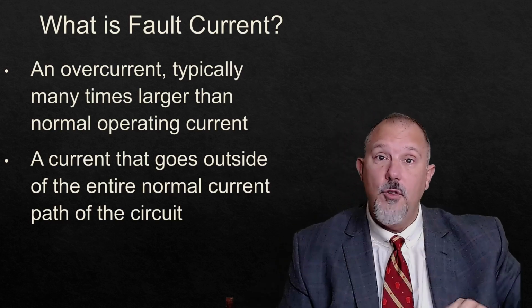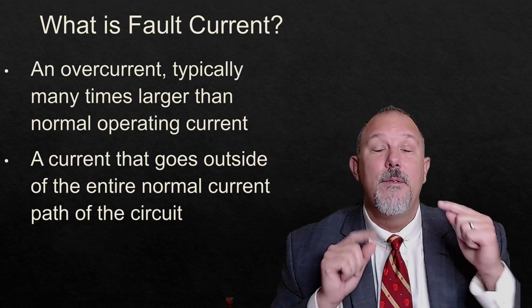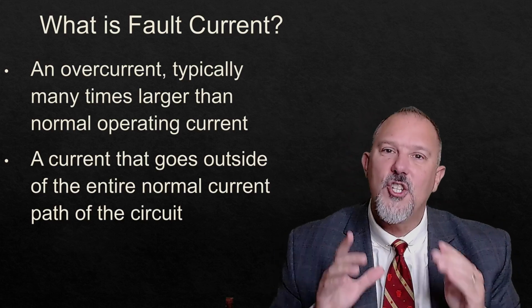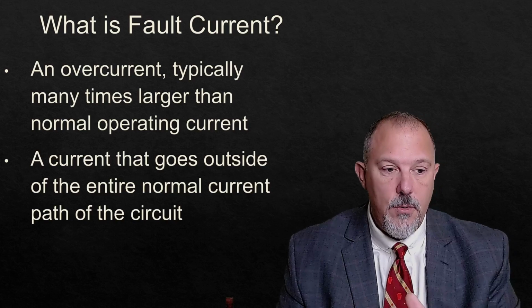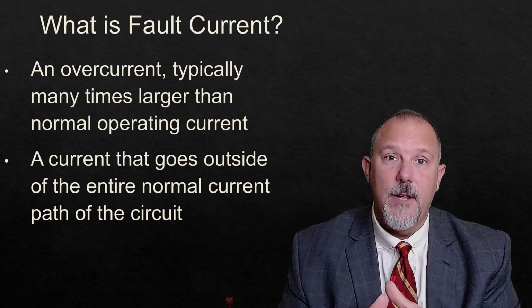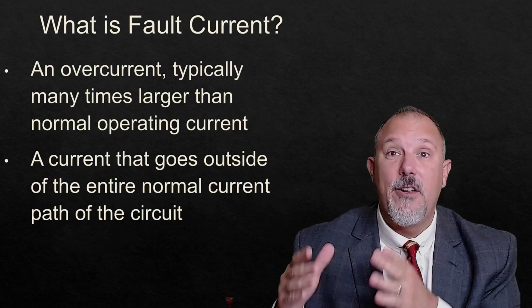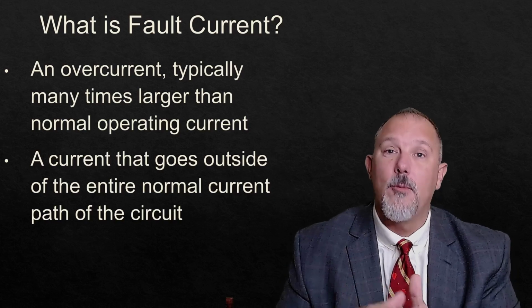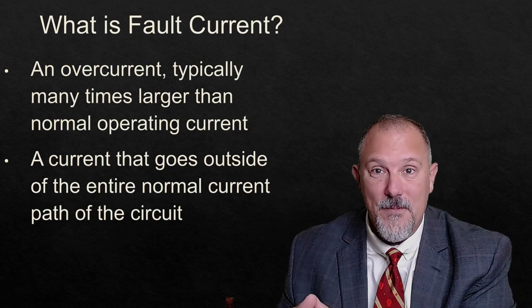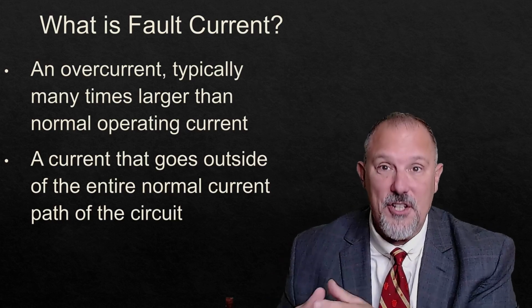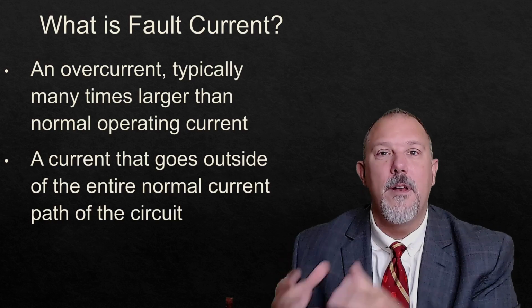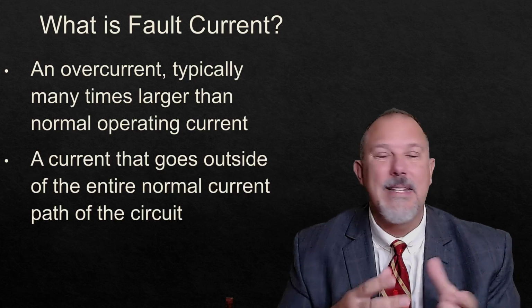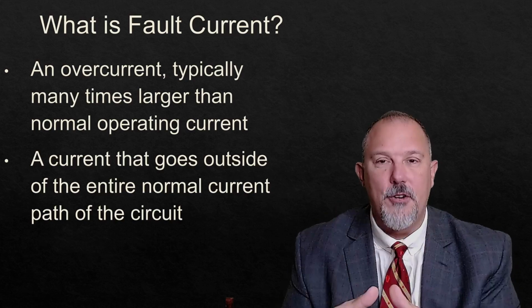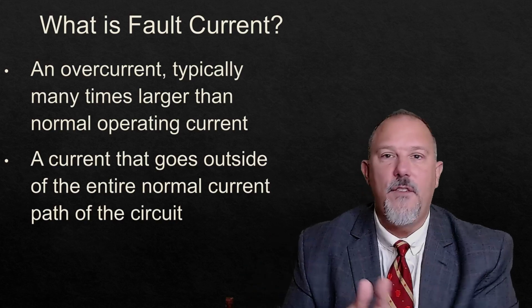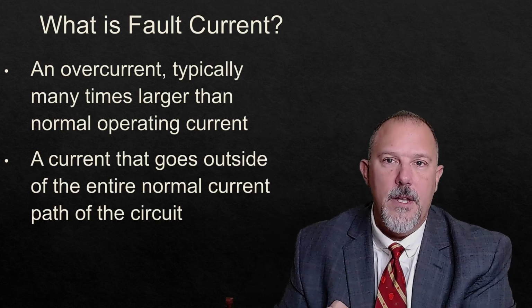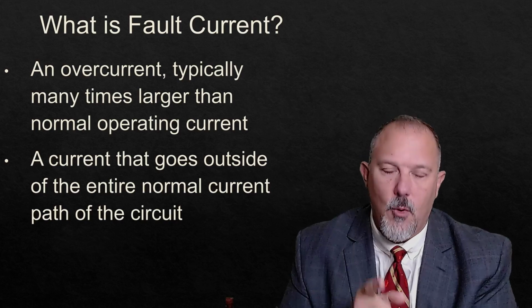Now, before you reset the overcurrent protective device, you have to understand how much current it saw. Because if a circuit breaker experiences close to its interrupting rating, you're probably going to want to take that circuit breaker out, evaluate its condition before you put it back into service. You may want to take it out, replace it with a new one, and get the removed breaker evaluated.